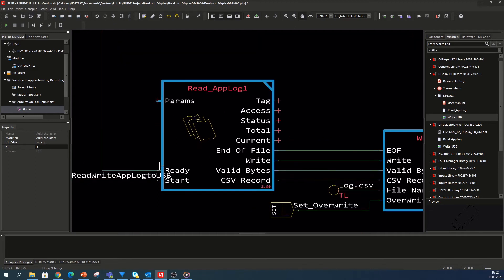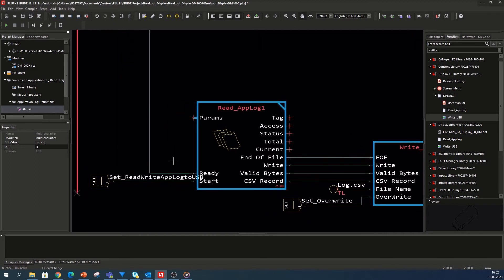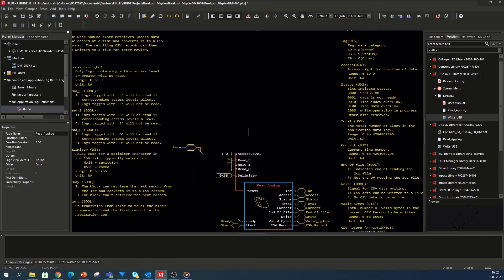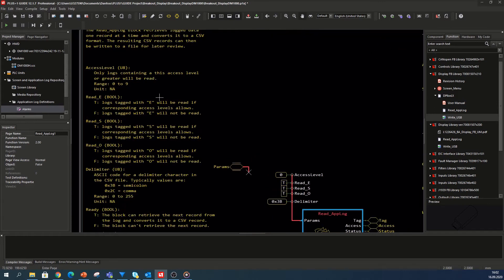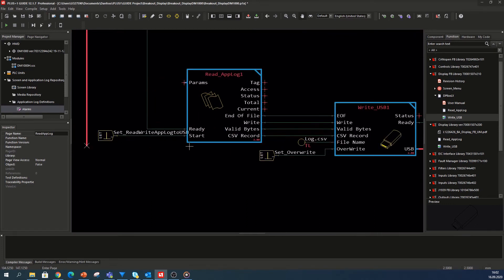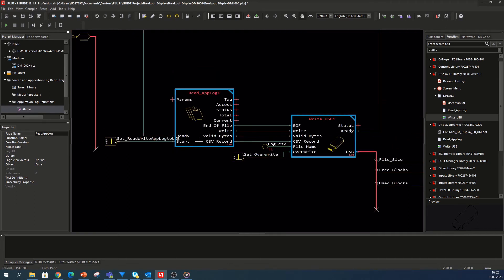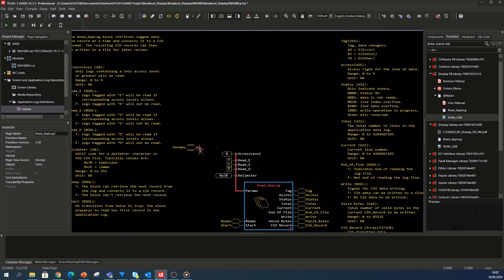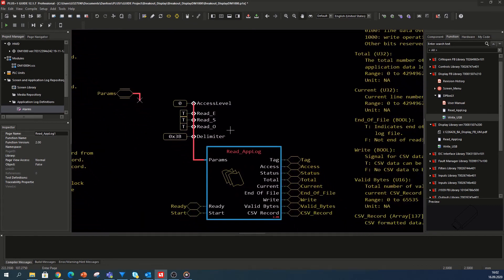The overwrite input can be connected with a boolean trigger signal forced via a display button, for example. Last but not least, the ready output from the write USB block needs to be connected with the ready input signal at the read app block. Since the read app block starts with the first record in the controller's application log and then reads the next record and so on, the feedback from the write USB block is necessary to avoid any overlap of reading and writing. With this output-input feedback signal, both blocks are synchronized perfectly. I keep the parameter input untouched and use the default constant settings inside the read app block page. Here you have the possibility to set up specific categories and access levels to read out. I use the default settings, which means any access level and any category inside the application log will be read out.